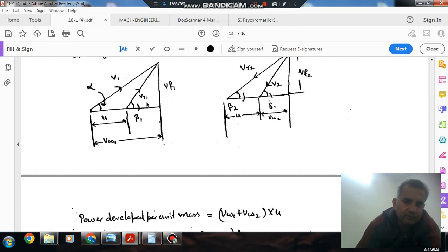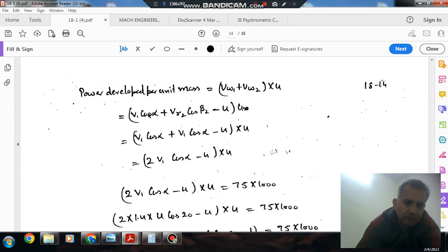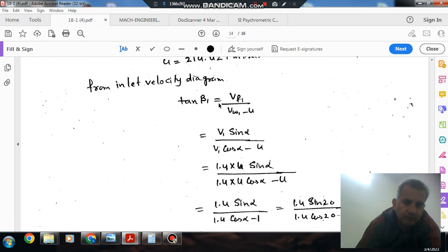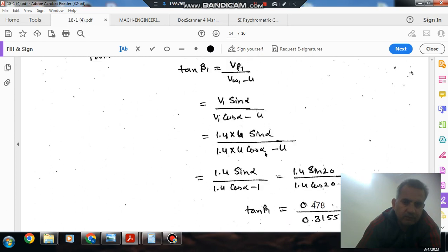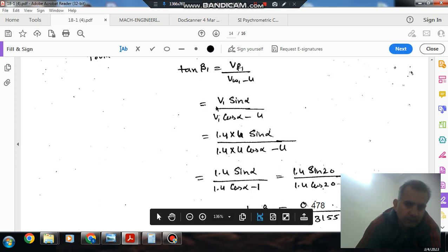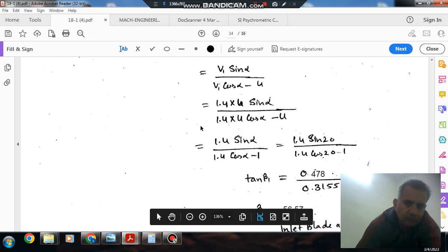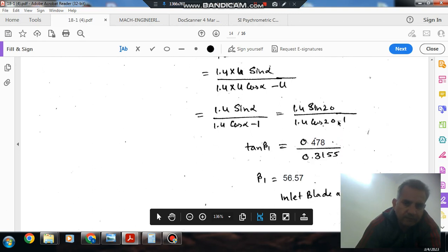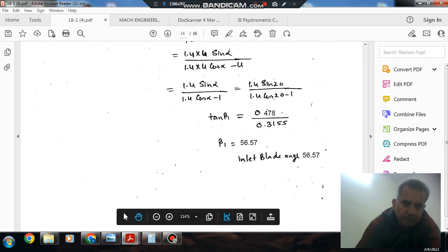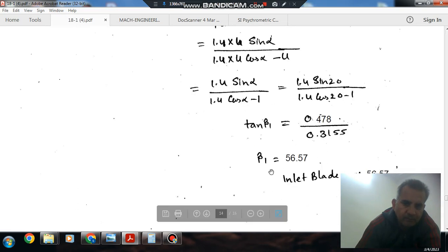From the inlet velocity diagram, tan beta1 equals Vf1 divided by Vw1 minus U. Vf1 equals V1 sin alpha and Vw1 equals V1 cos alpha. We can take U as common and cancel. Putting V1 equals 1.4U and solving, we get tan beta1, which gives beta1 equals 56.57 degrees.